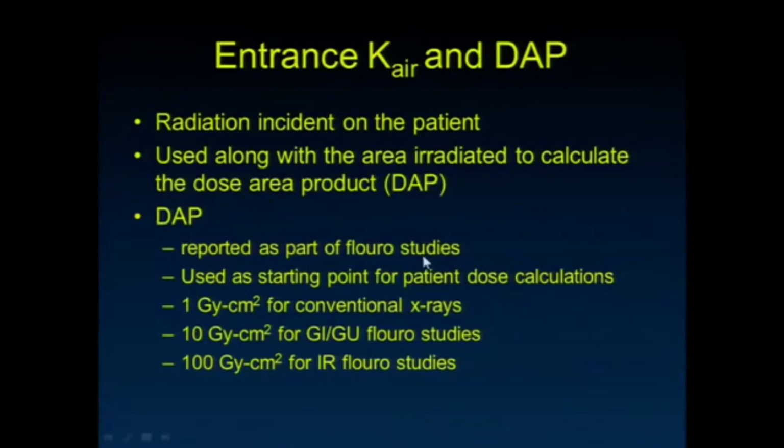It doesn't give you everything that you need. It tells you something about the energy in air at the entrance, just before the radiation entered the patient. It tells you something about the energy there, which in truth is closely related to the energy that's going to be deposited in the patient. But we need to know a few other things. It's helpful to know what the filtration was on the beam. What's the quality of our X-ray beam? This is really a little bit more of a measure of the quantity of that X-ray beam.